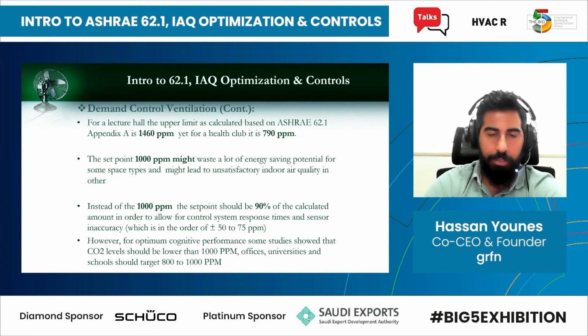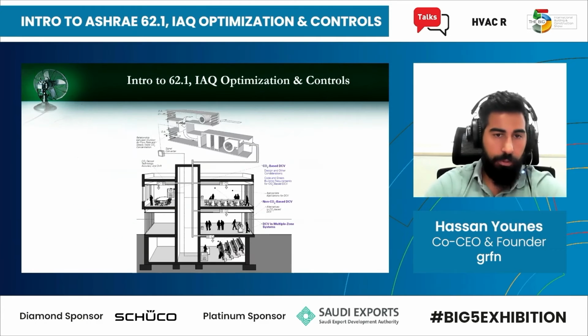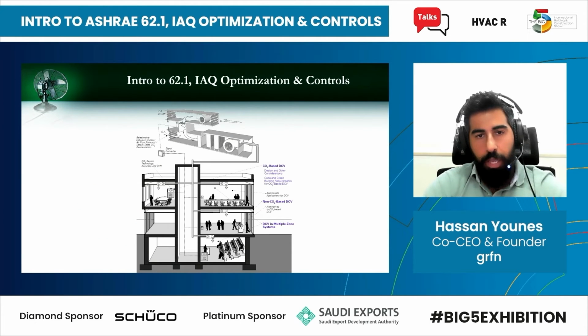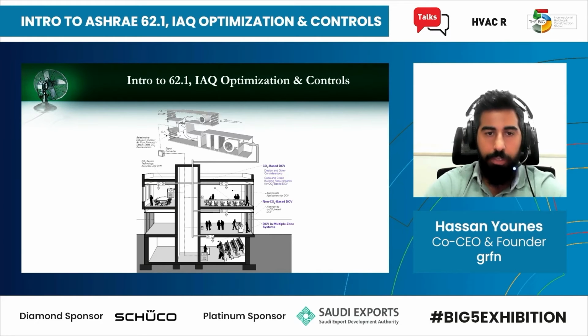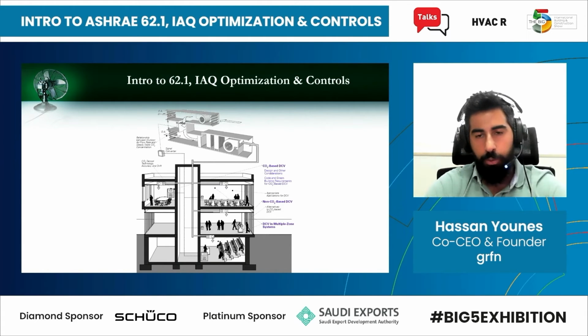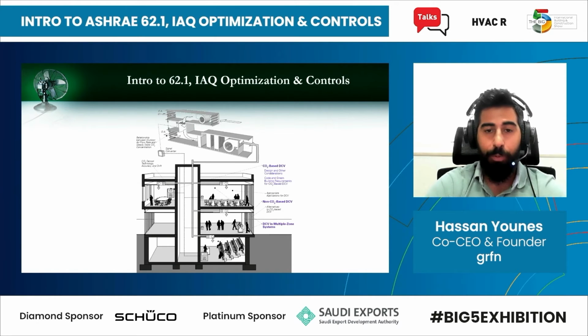But anywhere else, if you don't have a pandemic, you can increase the level of ppm as per the standard requirements. And that should be fine. You shouldn't face any issues in that. This is a schematic showing the outside air handling units connected to the different spaces, and you have CO2 sensors that are basically changing the amount of outside air that goes into every space. So we'd have a VAV box connected, and it will change the amount of outside air based on the CO2 levels. If the CO2 levels go higher than the set point, then the VAV damper will open and more outside air will come into that room.